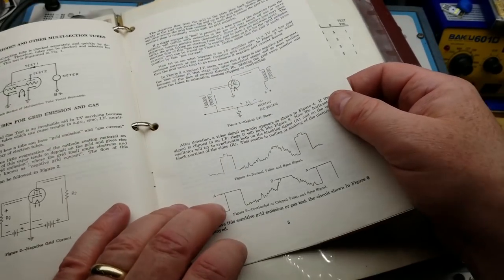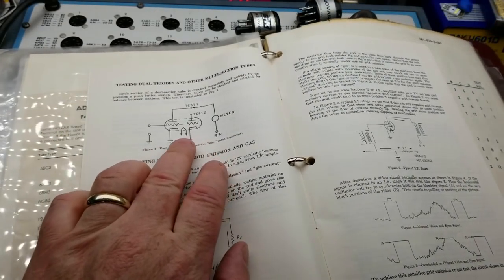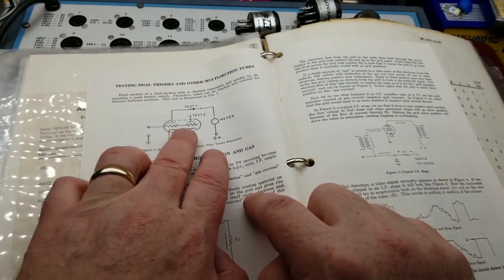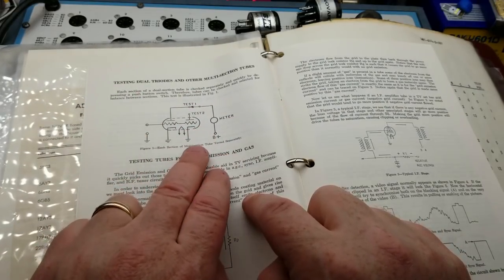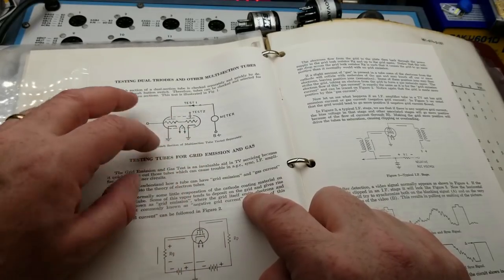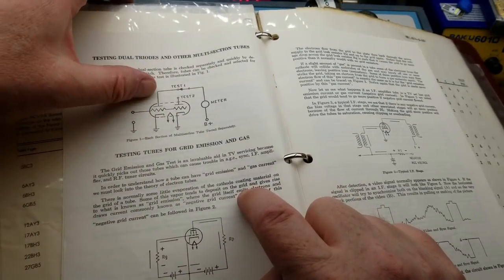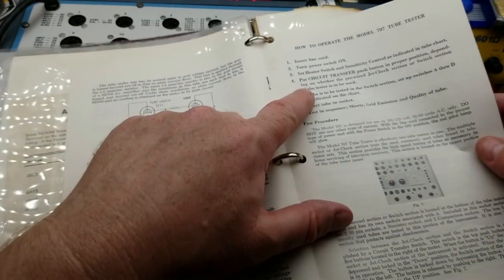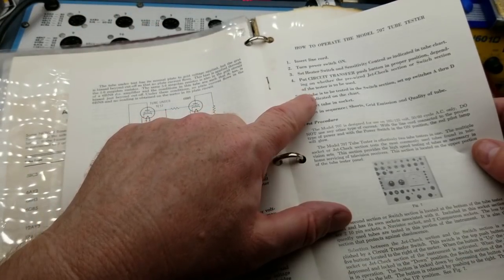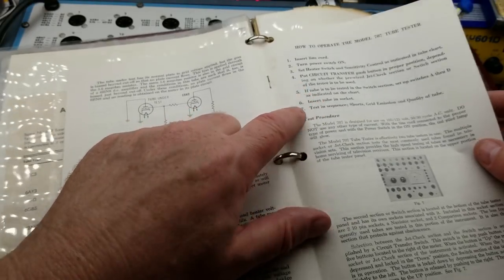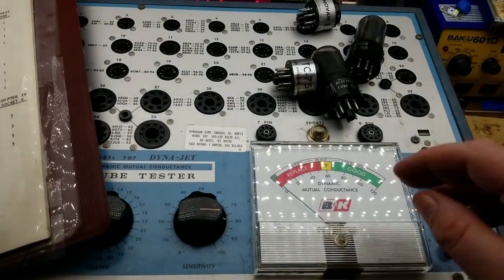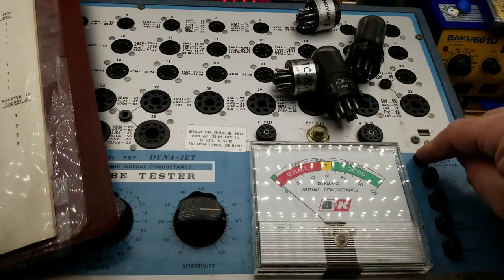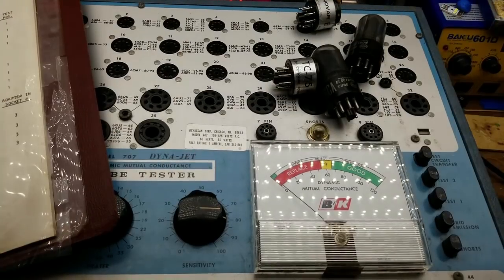And this goes through some of the math and some of the explanation of what's going on in the test. Oh yeah, here's one of those dual triodes that I was mentioning, a dual section tube. So that's what the test one and test two does I guess, test one tests the first section, test two tests the second section. Okay, circuit transfer push button in the proper position depending on whether you're using the pre-wired or the switch selection section.